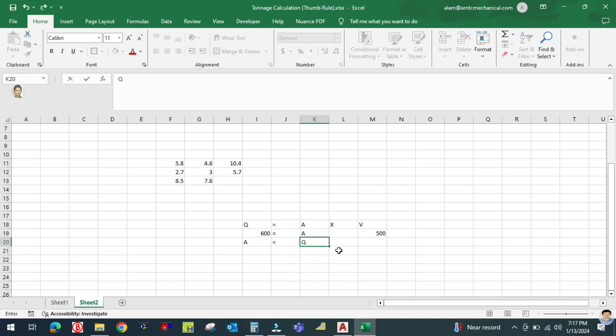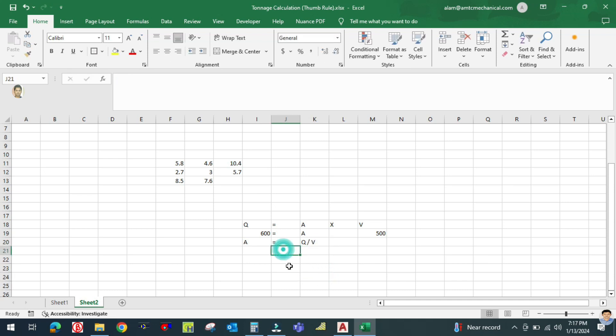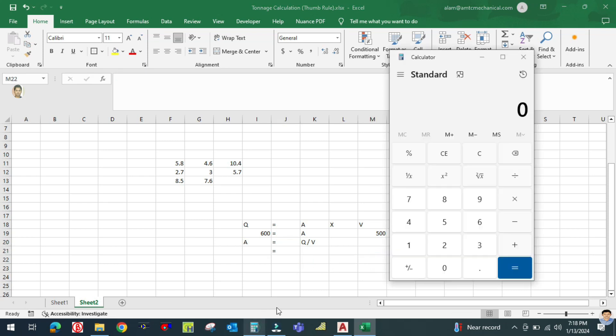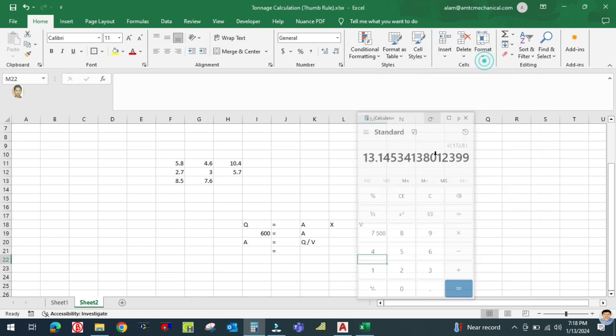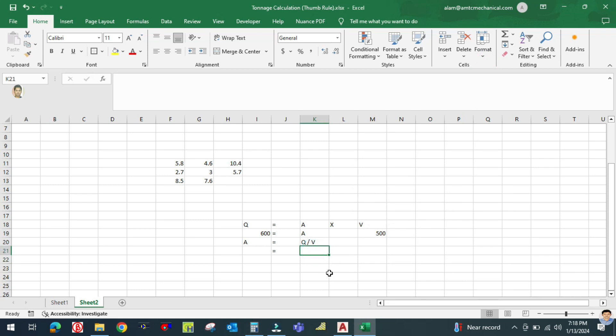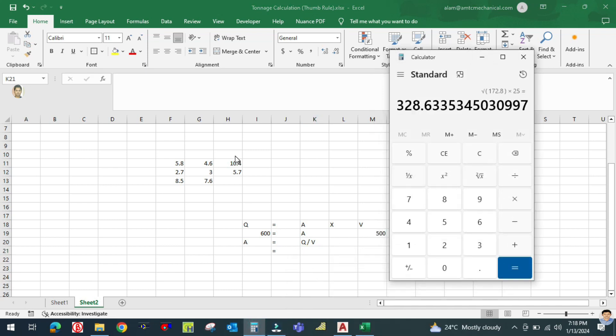Area equals Q divided by V. Q is 600, V is 500, so area equals 1.2 square feet. Convert to square inches by multiplying by 144. The square root gives 13 inches, so the diffuser size is 13 inches by 13 inches.